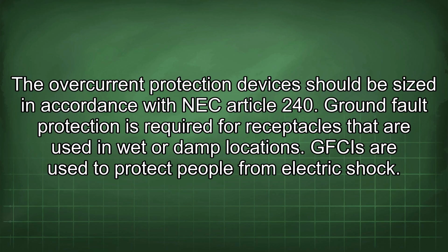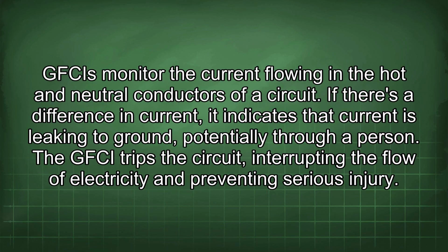Ground fault protection is required for receptacles that are used in wet or damp locations. GFCIs are used to protect people from electric shock. GFCIs monitor the current flowing in the hot and neutral conductors of a circuit. If there is a difference in current, it indicates that current is leaking to ground, potentially through a person. The GFCI trips the circuit, interrupting the flow of electricity and preventing serious injury.